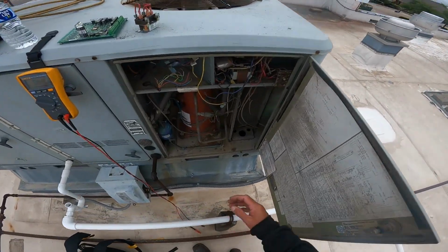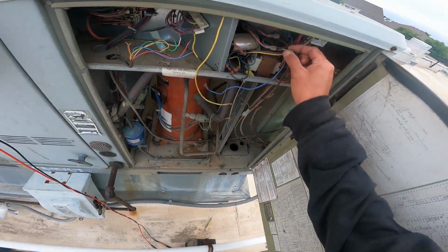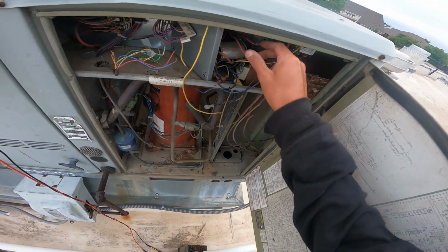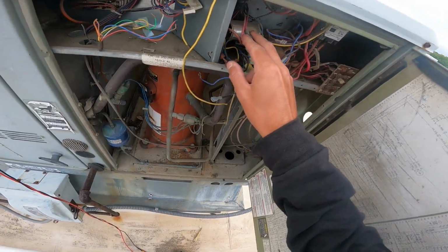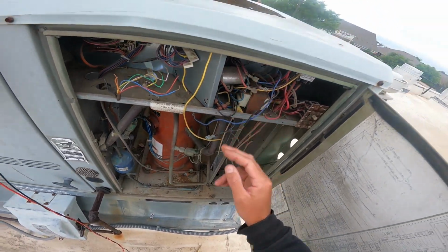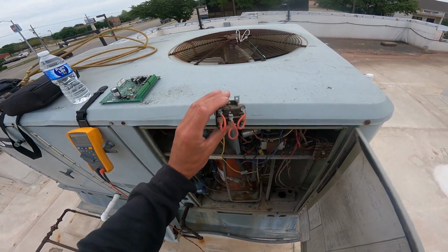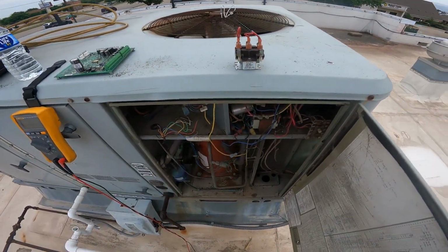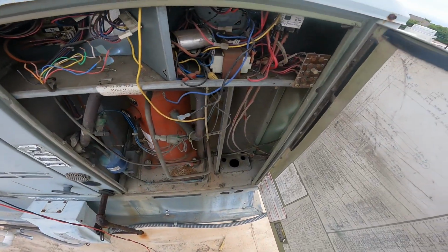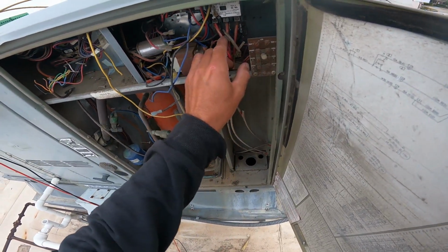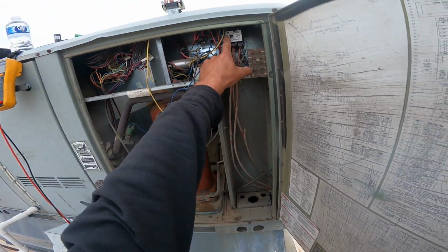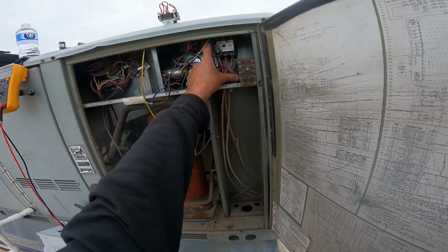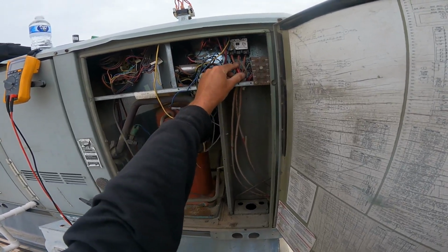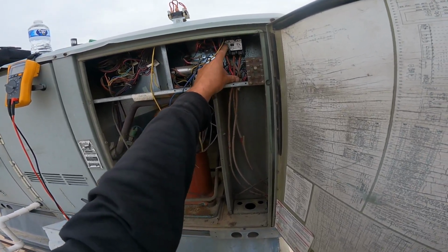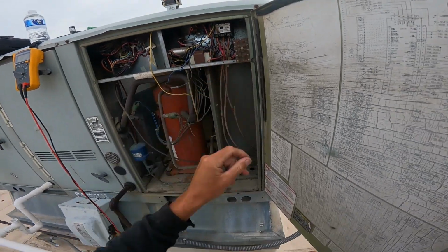I got wires hanging off everywhere, guys. This is a common, these are 2 low voltage hots. I know what they went to, they went to that relay right there. My contactor's got a little charring right here on this leg, but I don't see the wires charred, so I'm gonna let it roll. Not worried about the paper charring.